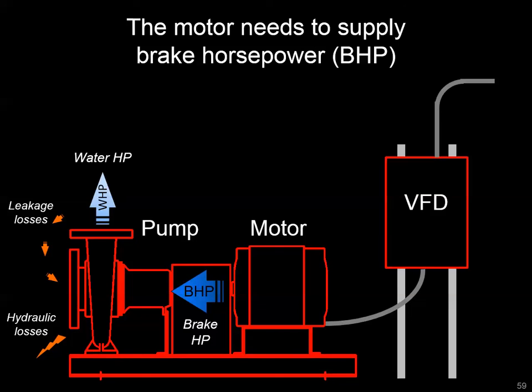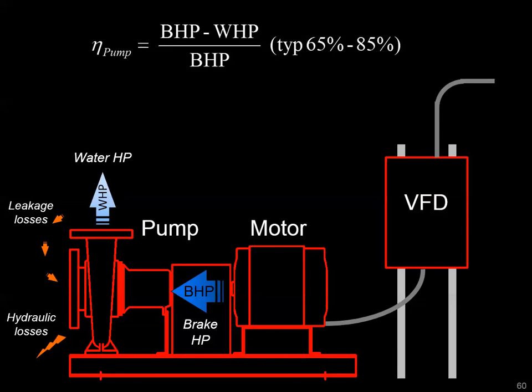A way to remember brake horsepower: it's the amount of power it would take to stop the spinning drive shaft between the motor and the pump. The difference between brake horsepower and water horsepower corresponds to the actual efficiency of the pump. Typical values you'll see on pump curves might be 65, 70, or 75 percent efficient, but it really depends on how the pump was sized and where on the pump curve it's operating — we'll look at that in a future video.